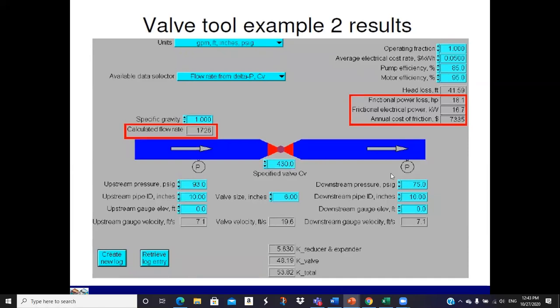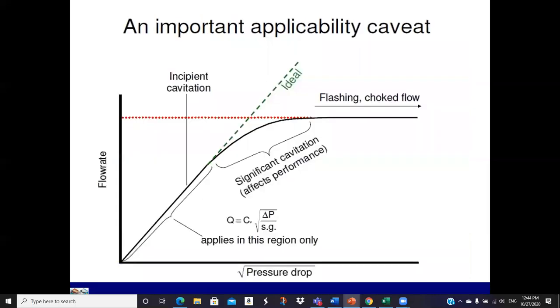you have the pressures, you have the CV, so now we're going to calculate flow rate from delta P and CV. This produces a flow rate of 1726, I believe that is. We've estimated our pump and motor efficiencies, electrical cost, all this. And so we're saying that the frictional loss is 18 horsepower, 16.7 kW, $7335 per year being dropped across that. So it's nothing you can't do by hand, but it's a pretty handy calculator-type tool. It's out there. Okay, we'll do this one then.